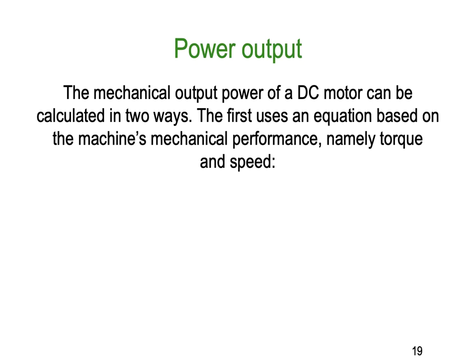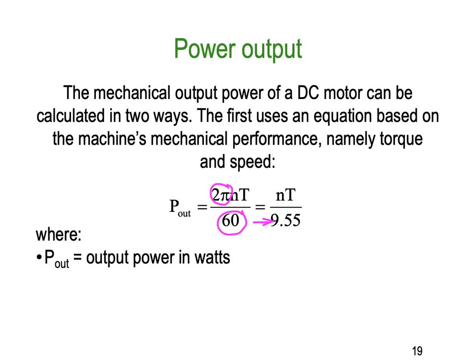The mechanical output power of a DC motor can be calculated two ways. The first uses torque and speed: P_out = 2πNT / 60, or equivalently NT / 9.55, where the constants 2π and 60 are combined into the denominator 9.55. Output power is in watts, speed N is in RPM, and torque T is in newton metres.